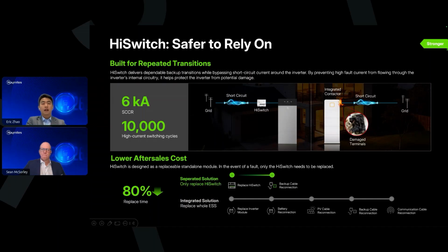Second, HiSwitch is a standalone replaceable module. So if the HiSwitch itself is damaged, the installer does not need to replace the complete ESS. The inverter and battery can remain in place and will not be impacted by the HiSwitch failure. Only the HiSwitch needs to be replaced, which reduces the number of components that need to be disconnected and reconnected, significantly reducing after-sales work.